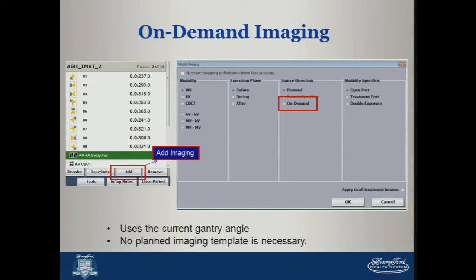So in terms of on-demand imaging, here's the kind of thing you would see at the console. You're just adding the imaging on an ad hoc basis because you want to, for example, you're concerned the patient might have shifted, or you want to verify setup, etc. So we use this, for example, in SRS treatments with couch kicks to check the patient setup at each new couch angle before beaming on. So flexible and useful capability that's added in this latest version of TrueBeam software.